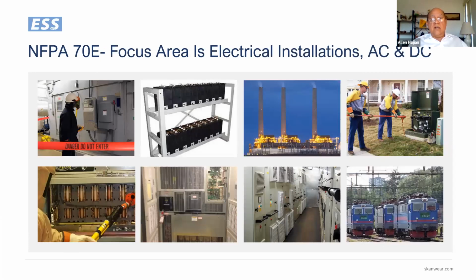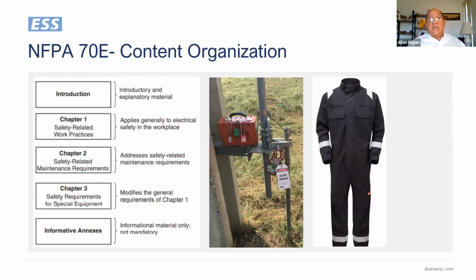It applies to regular electrical distribution equipment, whether they're AC or DC. Electrical distribution equipment in a factory, in a data center. And what it doesn't apply to is the generating station itself or the equipment that's directly under the utility. And also the shipboard equipment and the distribution equipment for the train. However, in the shipboard equipment and in the equipment under the direction of utility, NFPA 70E has been used very successfully. It's organized in 3 main chapters plus introduction and informative annexes. Chapter 1 is probably the most important one, which covers the electrical safe work practices.